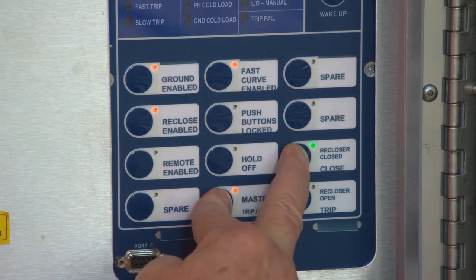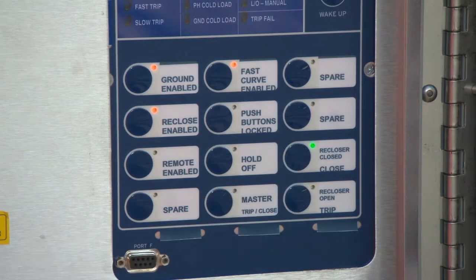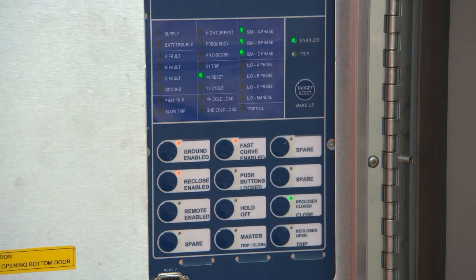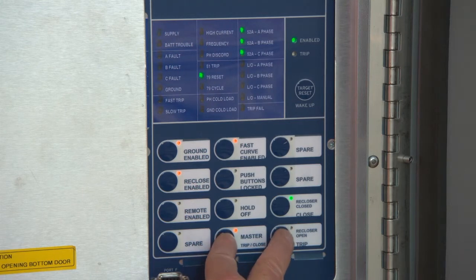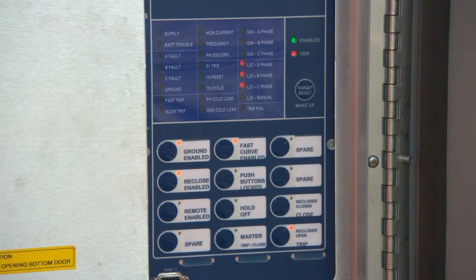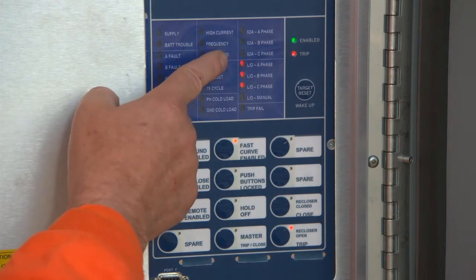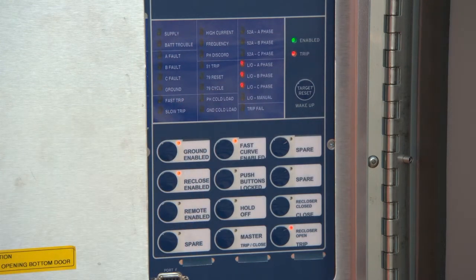To close it back in, push the master and the close button simultaneously. The reclose LED will turn green. Changing the recloser to an open state is a 2-button operation. Push the master button and the trip button together. The unit will trip open and the open indicator LED will turn red. Above you will see the 3 phases have locked out and all of the 3 LEDs have turned red.